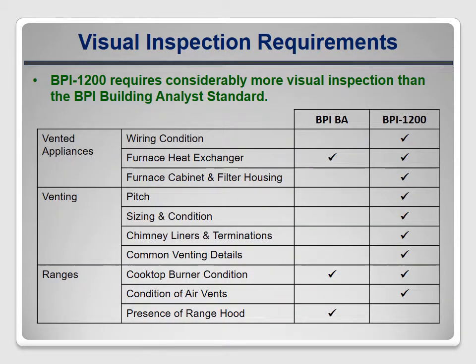On the other hand, the BA Standard requires that the house be inspected for the presence of carbon monoxide detectors, and this is not included in BPI 1200. BPI 1200 requires an assessment of vented appliance wiring, as well as heat exchangers, cabinets, and filter housings on forced air heating systems, while the BA Standard only requires a heat exchanger inspection.